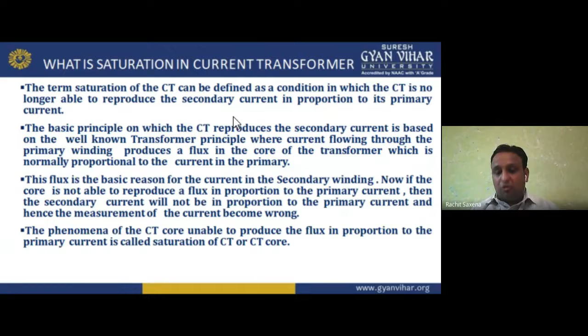Now, if the core is not able to reproduce a flux in proportion to the primary current, then the secondary current will not be in proportion to the primary current, and hence the measurement of current becomes wrong. If the secondary is not proportional to the primary, the reading will be wrong. The phenomenon of the CT core being unable to produce flux in proportion to the primary current is called saturation of the CT core.